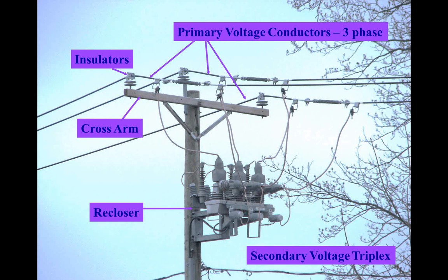Your lights just went out the second time, and now it's going to wait 30 seconds. It says, I'm going to give it one more shot to try to clear this problem and keep the customer's lights on. Boom, it closes back in, your lights came back on, it's trying to burn off or clear whatever the issue is. If it cannot clear the fault, it'll open up that third time. These things are designed for what we call three shots to a lockout. So if your lights go on and off, on and off, on and off, that's a recloser doing that to you.